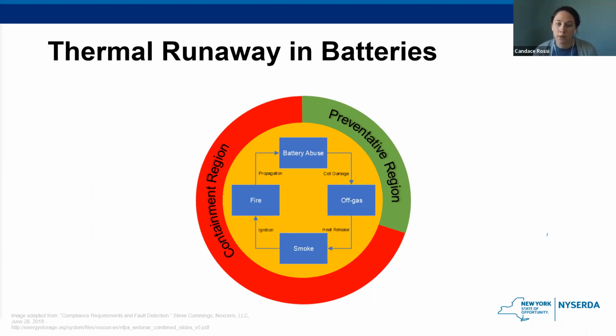And once thermal runaway has been started, it really cannot be stopped. So the energy storage needs to have a device that can recognize when the temperature is rising, and the device should isolate the area and send a signal to the owner of the system that a problem exists. When there is battery abuse or off-gassing, there's still time to prevent the spread of a thermal runaway event. But once smoke or fire is visible, it's clear that a thermal runaway is underway and it'll just need to be contained.